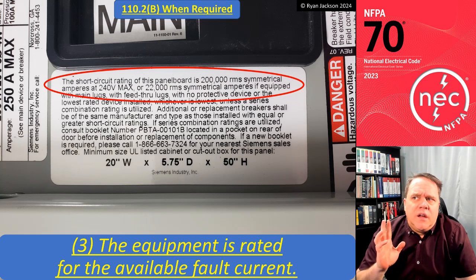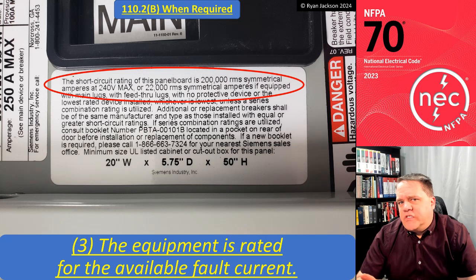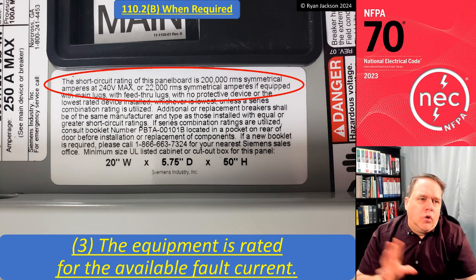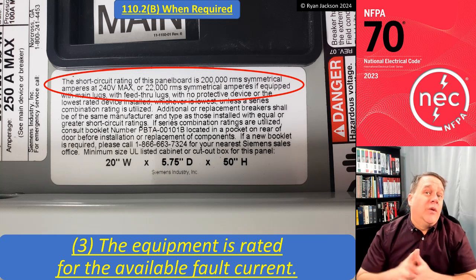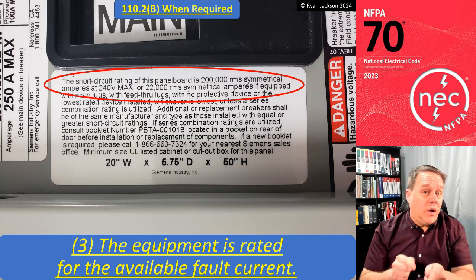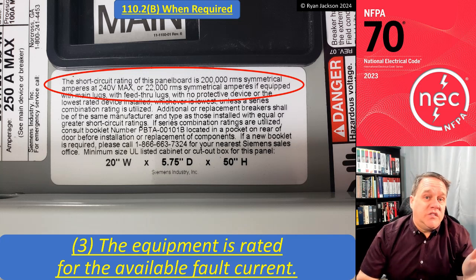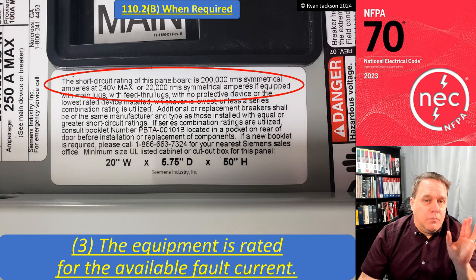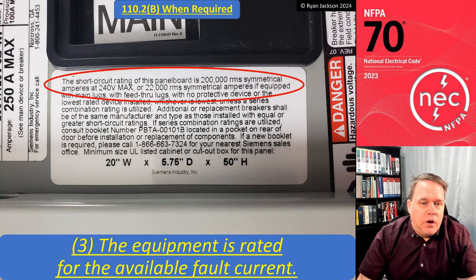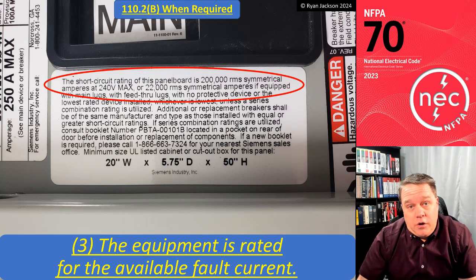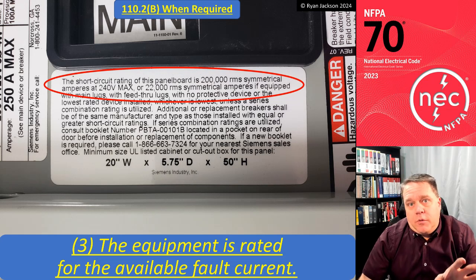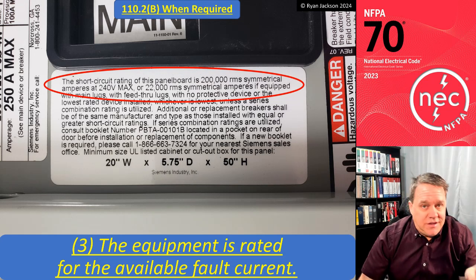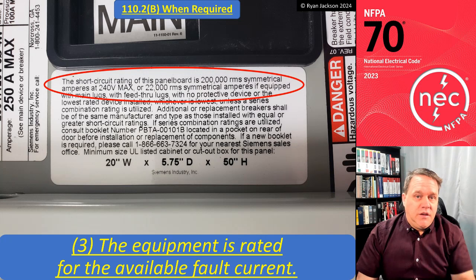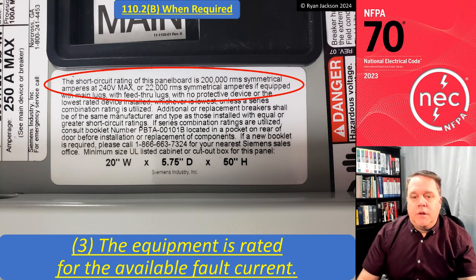This is easier in a modern installation than it was in older installations because now under the 2020 National Electrical Code, 408.6 says you need to mark the available fault current at every panel board. So determining the available fault current is a lot easier today than it was in yesteryear. So make sure the equipment is rated for the fault current.